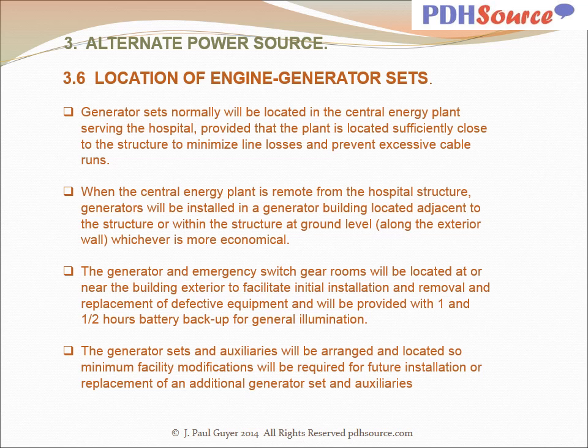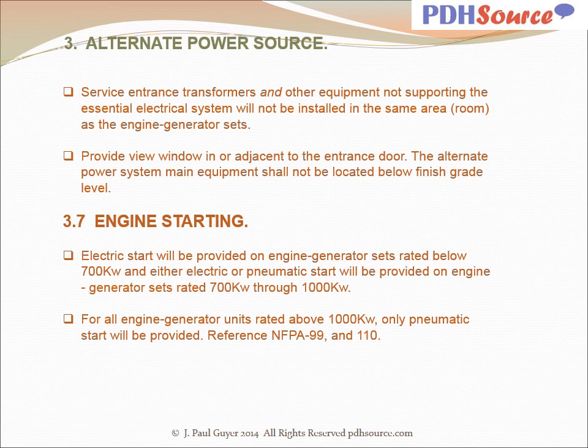The generator and emergency switchgear rooms will be located at or near the building exterior to facilitate initial installation and removal and replacement of defective equipment, and will be provided with 1.5 hours battery backup for general illumination. The generator sets and auxiliaries will be arranged and located so minimum facility modifications will be required for future installation or replacement of an additional generator set and auxiliaries.